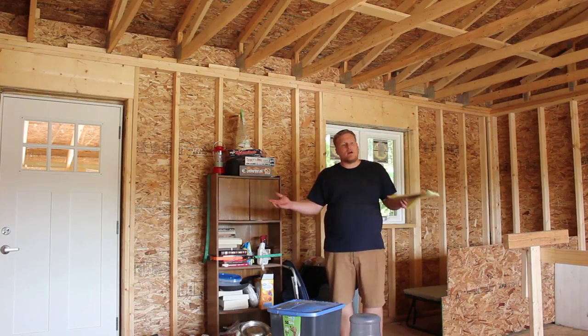Now I'm going to quickly go over some of the BTU requirements that I calculated for all of our walls, windows, doors, ceiling, and floor. R40 walls, 1,477 BTUs. Now this is heating up to 68 degrees Fahrenheit inside with a 5 degree temperature outside. Ceiling, 896 BTUs. Floor, 1,493 BTUs. Windows, 1,228 BTUs. Door, 278 BTUs.